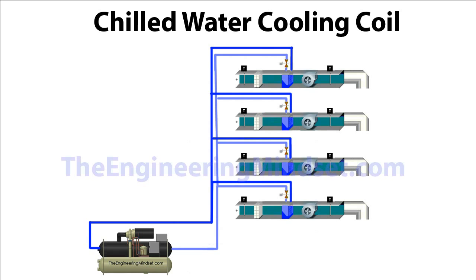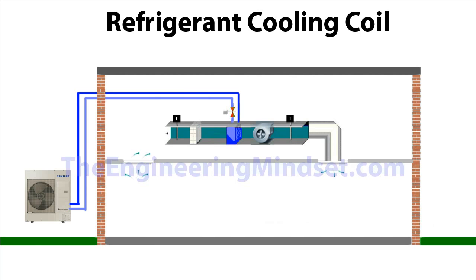The other form of cooling coil is the chilled water cooling coil. From an economical point of view, if you've got multiple AHUs, fan coil units, or a lot of cooling demand on the building, it's probably going to be more economical to have a centralized system rather than a localized direct expansion unit. This setup is more common in very large buildings, whereas the DX setup is much more common in shops or small sites and buildings.